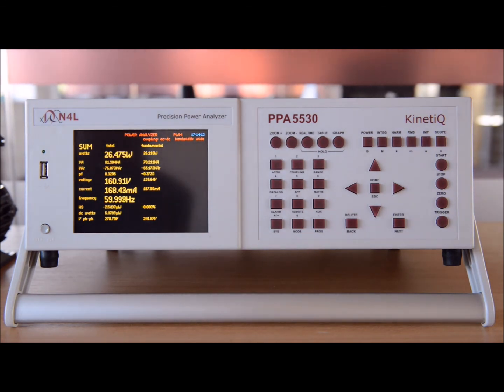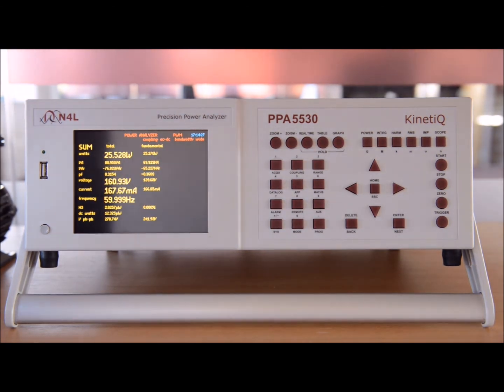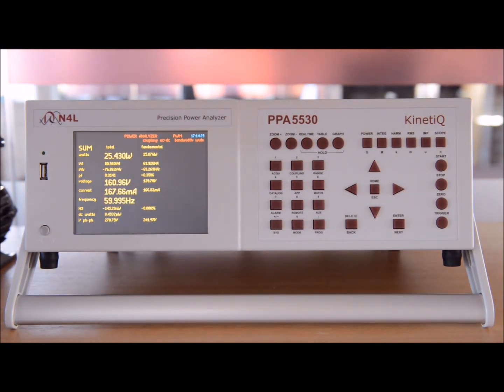Okay, so it's not a fixed window. This instrument is synchronized to the fundamental frequency. That's how we achieve such phenomenal high frequency accuracy. So you'll be able to change and track the window as the frequency changes.